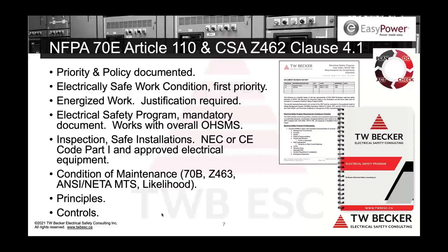And then we need safe installations, and we need inspection of those installations, National Electrical Code or CE Code Part 1, with approved electrical equipment. And there are some other key requirements in the NEC related to arc flash specifically that aren't in the CE Code Part 1. So that's your starting position, and your electrical safety program should indicate that you're going to comply with those requirements. Well, that's also related to risk. Then condition of maintenance, again, this is NFPA 70B and CSA Z463 and ANSI NETA MTS, also needs to be identified in your electrical safety program, and that impacts risk again with respect to likelihood of occurrence.